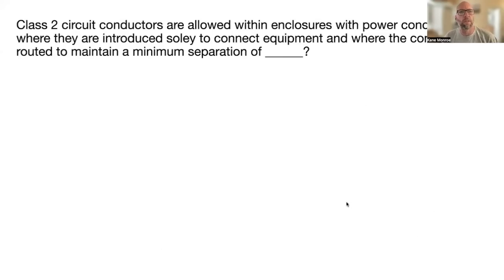Class 2 circuit conductors are allowed within an enclosure with power conductors only where they are introduced solely to connect equipment and where the conductors are routed to maintain a minimum separation of 1/4 inch. NEC 725.136(D).